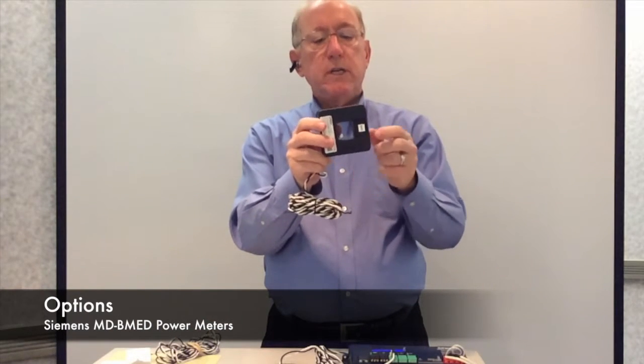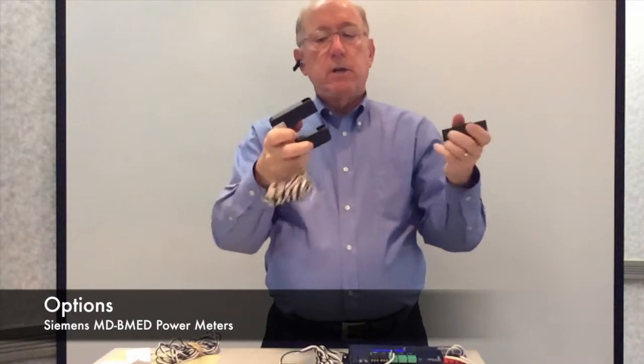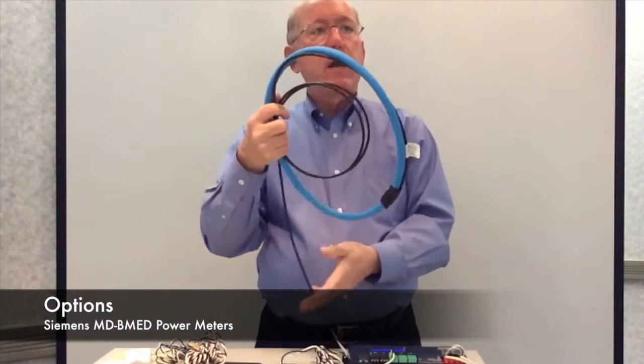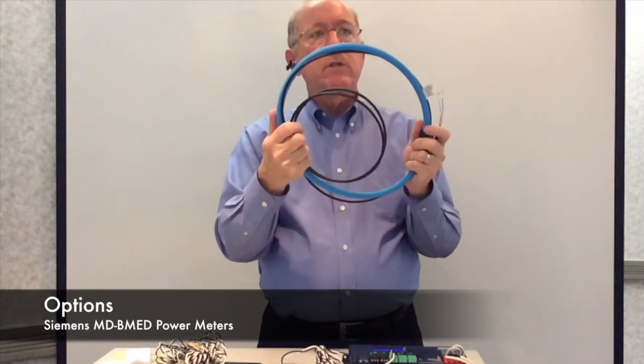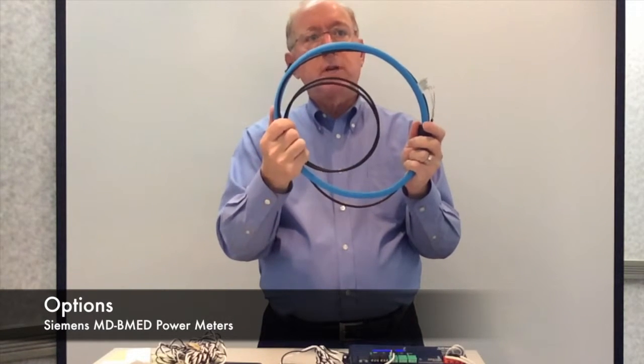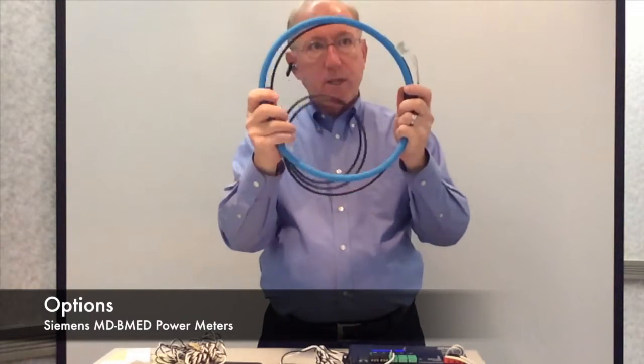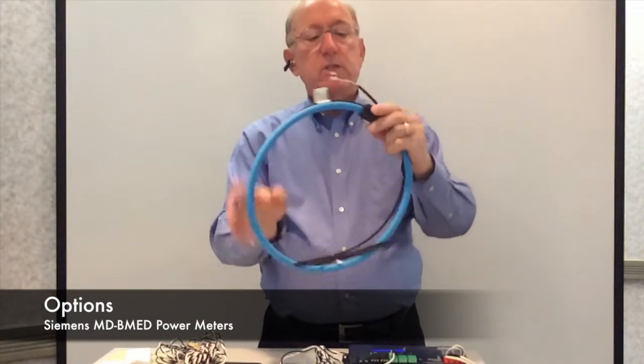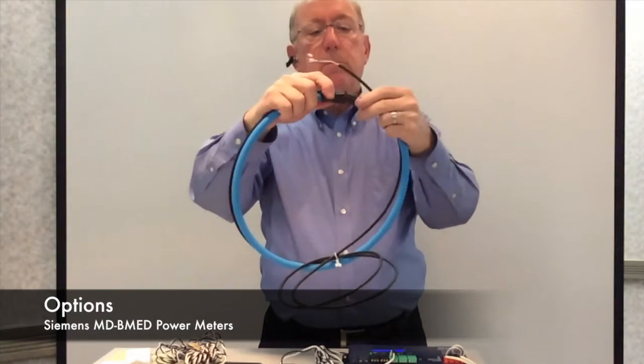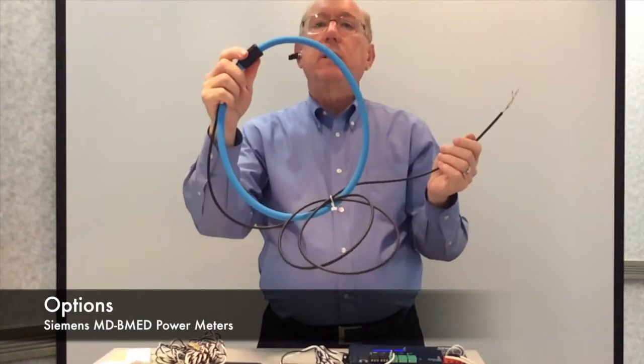And then finally for the larger applications where you get to 400 to 600 amp, a standard split core CT, again, very simple to wire in the field. Pull it open, install it around the wire, close it back up, and you're done. For bus bars or the like, where something like this is very difficult to get to, we have 2 different Rogowski coils. This is the larger at 36 inch. We have another one at 16 inch, which gives about a 5-inch diameter rather than this 10 inch. And it's made to very simply go around a circuit or a bus bar, connect in, making installation extremely easy.